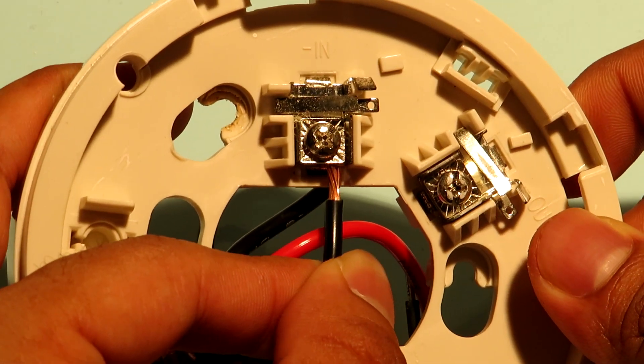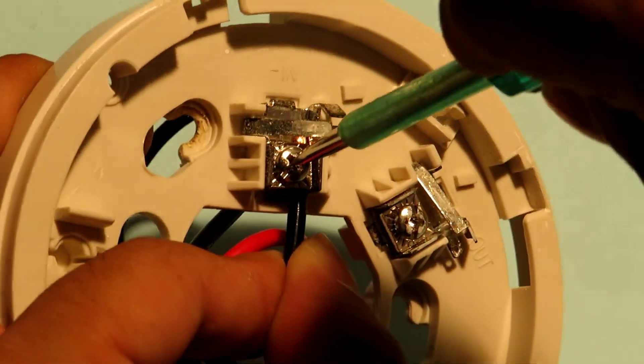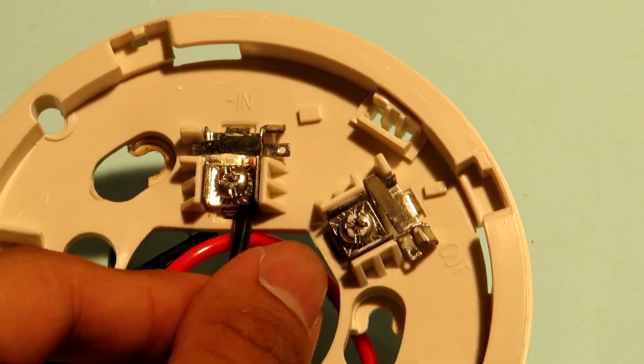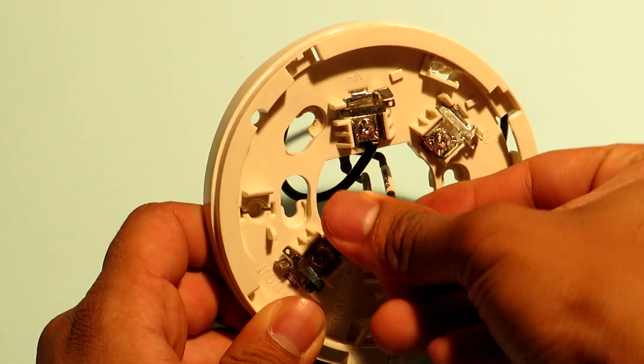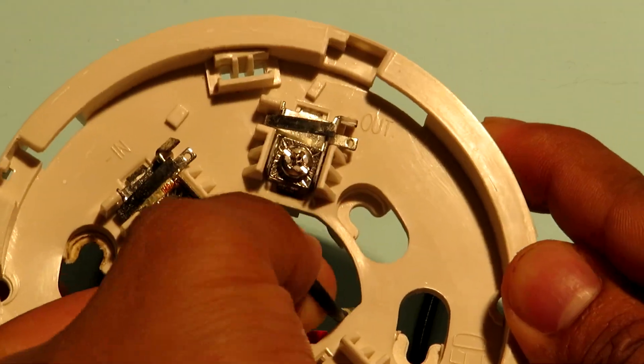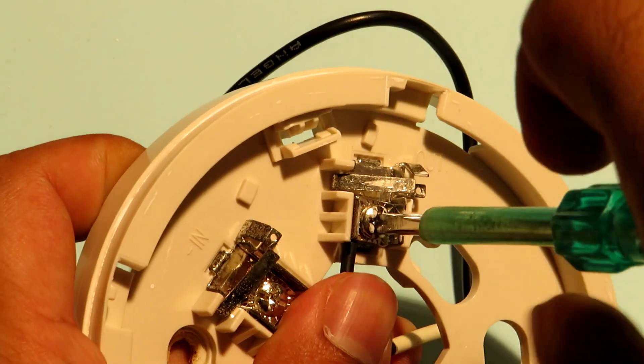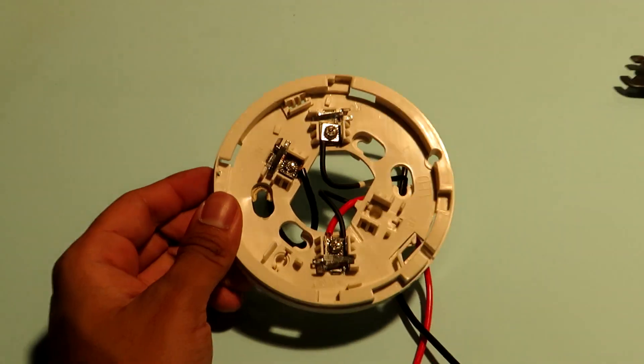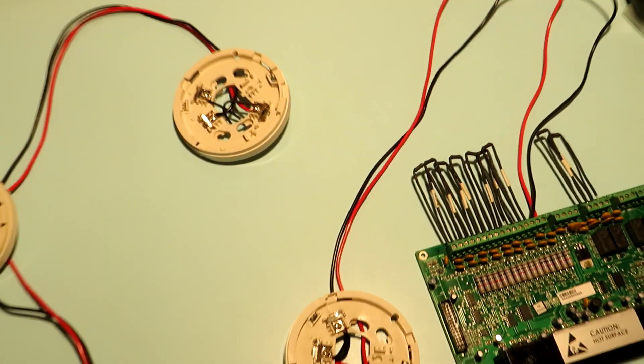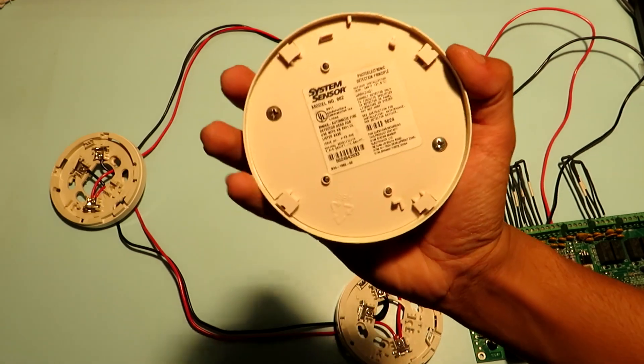The negative wire coming from the previous detector will go into the negative in terminal as usual. Now the last thing left to do is to connect the other end of our EOL resistor to the negative out terminal. In this way we are getting a fail safe mechanism so if anybody opens any detector in the line we'll get an indication in the panel. This also includes the last detector. So if someone opens the last detector also we are going to get an indication in the panel. So with this we have successfully connected the entire zone loop with our fire alarm control panel.